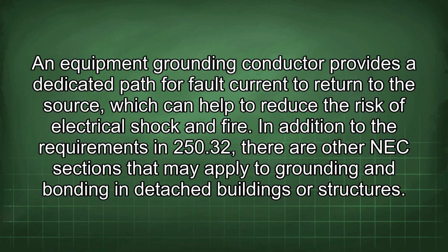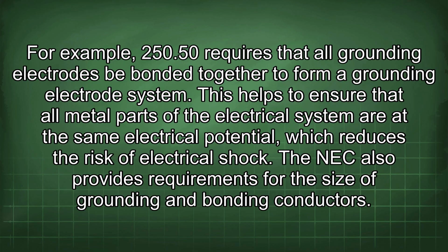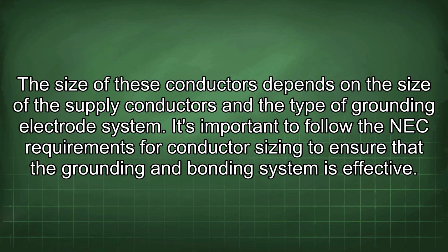In addition to the requirements in 250.32, there are other NEC sections that may apply to grounding and bonding in detached buildings or structures. For example, 250.50 requires that all grounding electrodes be bonded together to form a grounding electrode system. This helps to ensure that all metal parts of the electrical system are at the same electrical potential, which reduces the risk of electrical shock. The NEC also provides requirements for the size of grounding and bonding conductors. The size of these conductors depends on the size of the supply conductors and the type of grounding electrode system. It's important to follow the NEC requirements for conductor sizing to ensure that the grounding and bonding system is effective.